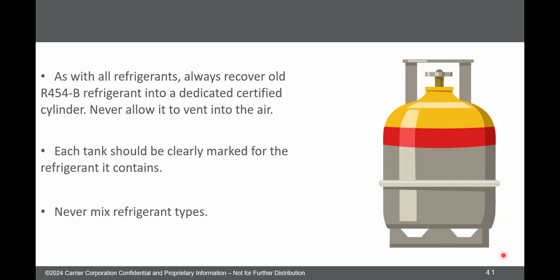Reclaim cylinders, as mentioned, left-hand threaded, painted yellow, red band on them. Ideally, people would not mix refrigerants in them. You definitely cannot put A2Ls into a regular reclaim cylinder. It has to go into one of these ones. I mean, you could do it. You could force it in there, right? But from a safety standpoint, it needs to be in the one that has the right safety controls on it.